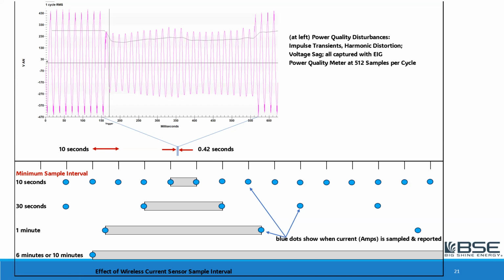They're just telling you an RMS value at a point in time, and unless it happens to exactly coincide with a big disturbance, you won't even know that anything's happening. And I want to show you also that this spiky stuff here, which is very damaging to electronics, is very hard to detect with, say, an electrician's voltage meter. Here we were sampling at 512 samples per electrical cycle. And actually our power quality meter, we can increase that to 1024.